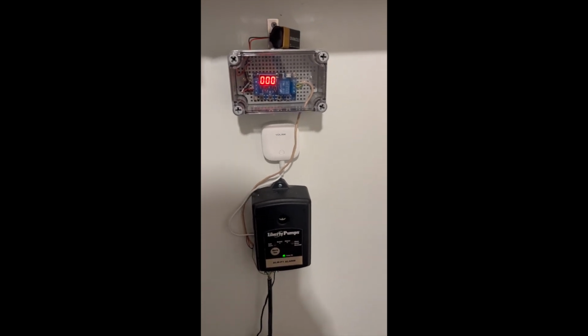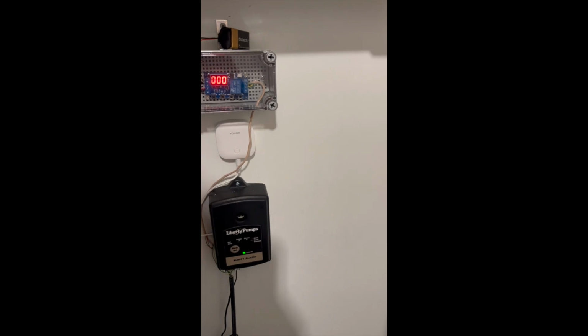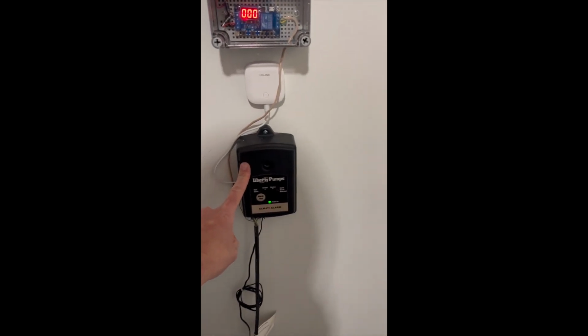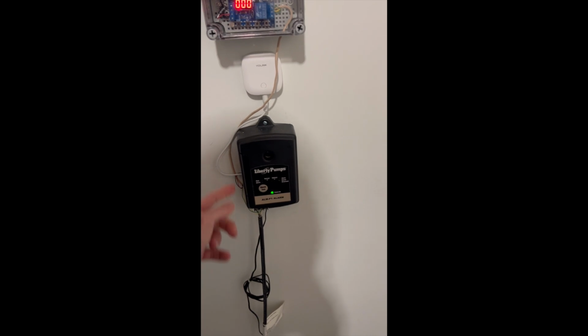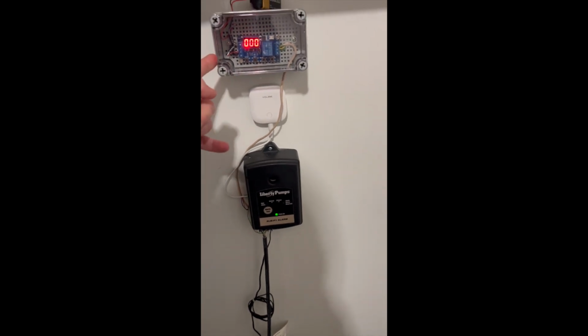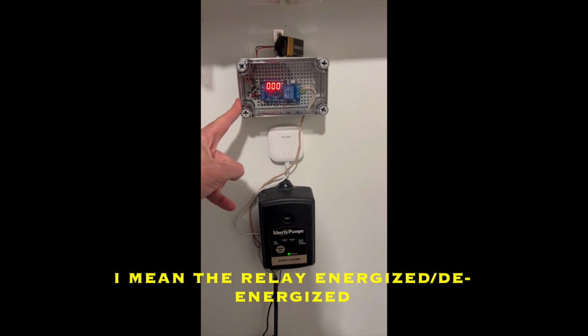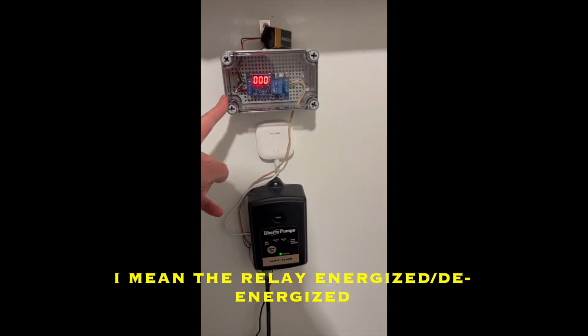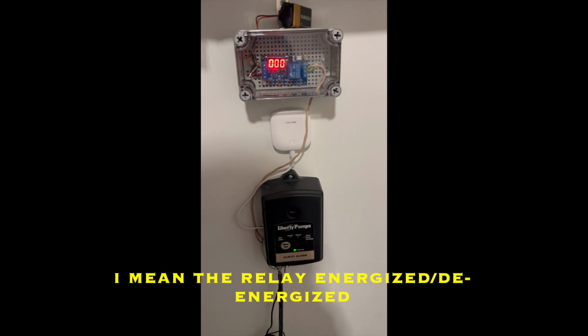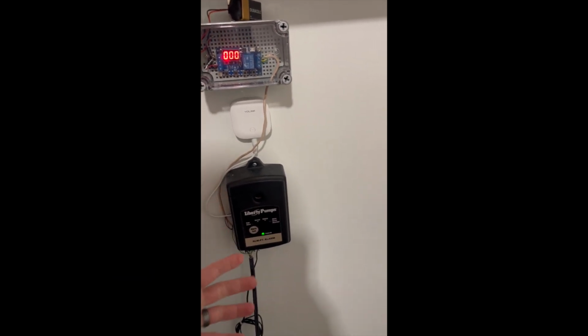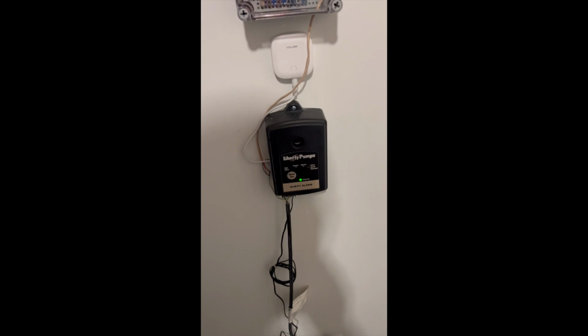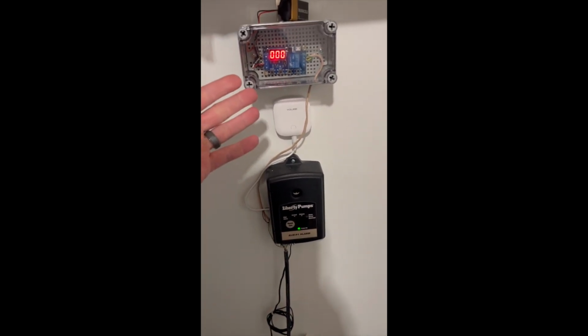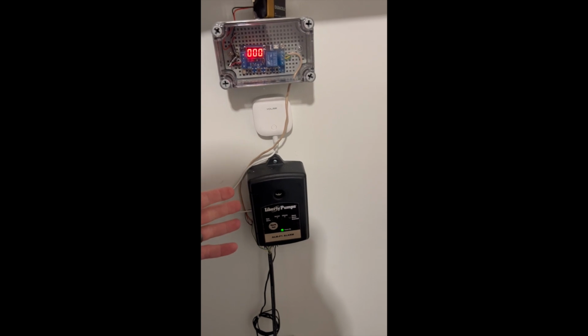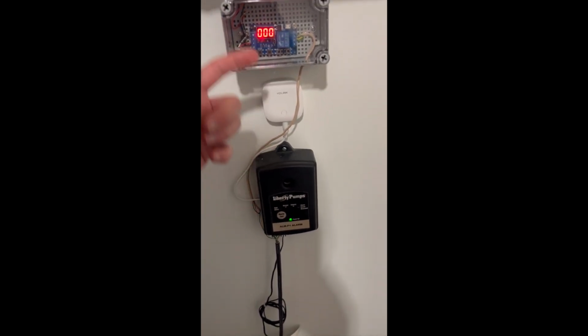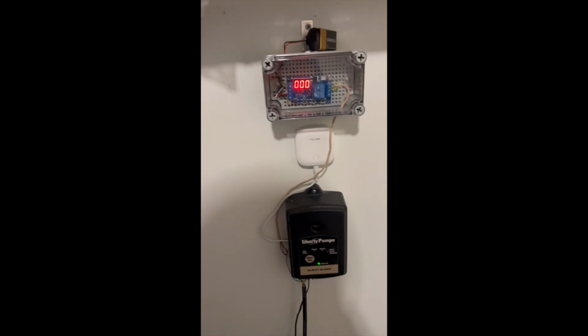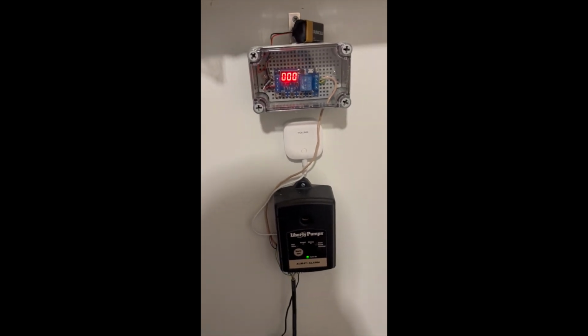And finally, on this wire, two other things. One, this pump alarm says it supports 100 milliamps of output on its auxiliary power. You remember this draws 96 with the relay closed, and 30 with the relay inactive. Because this unit will be unplugged in a power failure situation, and the relay will only be active in a power failure situation, we will never exceed 30 milliamps to this, because if it's in an alarm condition, it means we're being fed off the battery during that time.